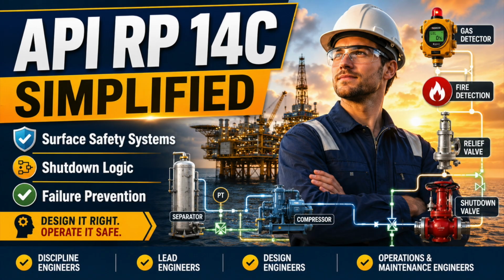For lead engineers and project managers, the greatest failure is treating surface safety as an instrumentation package. Process defines the hazard and set point basis. Mechanical defines equipment limits. Piping defines isolation and relief connectivity. Electrical defines hazardous area compliance and power survivability. Layout defines ventilation, access, and dispersion. Operations defines real lineups. Maintenance defines testability. Instrumentation integrates detection and action. The lead engineer must force these disciplines into one coherent system.